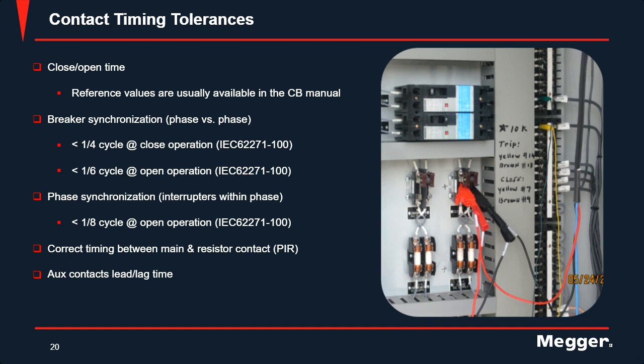So when we talk about contact timing tolerances, we have different tolerances. Usually for the close and open time, you can reference the user manual for the circuit breaker. In the absence of that user manual or manufacturer data, there are standards out there that put forth limits, like IEC 62271-100, that says for breaker synchronization, phase to phase, all phases should close within 1/4 cycle of each other, and all phases should open within 1/6 of a cycle of each other. And if you have any interrupters within the phase, they should be within 1/8 of a cycle of the opening operation.